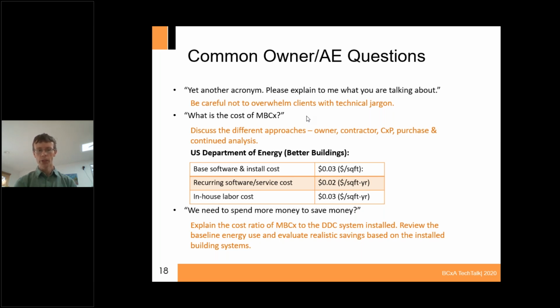You want to review their energy baseline use, whether it's already been modeled through LEED or not, and then evaluate how realistic the savings are going to be on that installed building. My gut feeling is the buildings we've done, which have been chiller, boiler-based, VAV air handling units, have a lot more that could be optimized than, say, your all-electric VRF system and DOAS units, which are probably going to be harder to find the same kind of savings in. So you would have to adjust your evaluation of how much you're going to save over time.